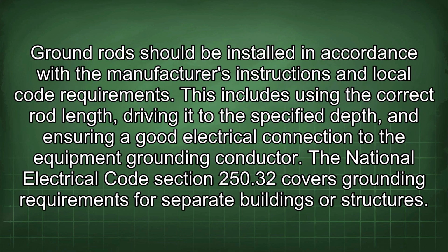Ground rods should be installed in accordance with the manufacturer's instructions and local code requirements. This includes using the correct rod length, driving it to the specified depth, and ensuring a good electrical connection to the equipment grounding conductor. The National Electrical Code Section 250.32 covers grounding requirements for separate buildings or structures.